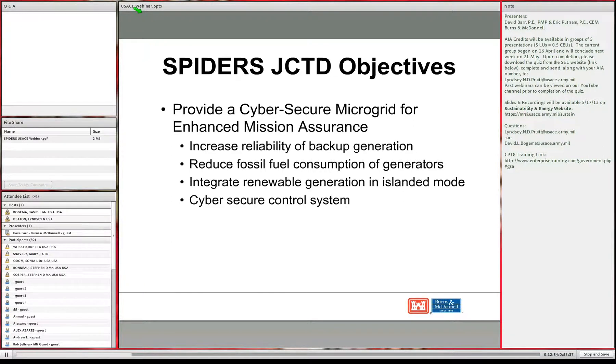SPIDERS is not reaching a perfect solution, but it gets a long way toward it—delivering benefits as cost-effectively as possible without spending money to prove something that isn't practical yet. A follow-up question asked whether SPIDERS induces more frequent changes to generation control assets, causing increased wear or maintenance. The answer is no—it actually benefits generators, as they are currently so lightly loaded that wet stacking occurs, which is detrimental. Running generators closer to their optimal rating makes them healthier and reduces long-term maintenance.